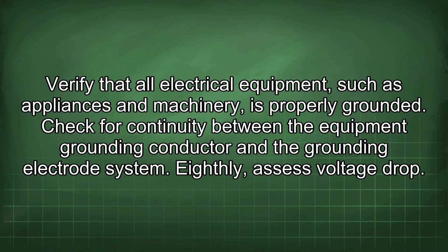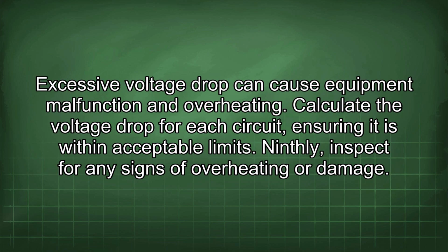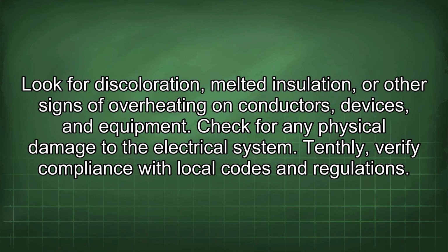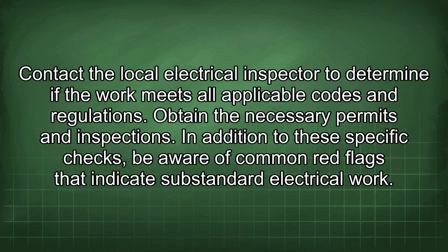Eighthly, assess voltage drop. Excessive voltage drop can cause equipment malfunction and overheating. Calculate the voltage drop for each circuit, ensuring it is within acceptable limits. Ninthly, inspect for any signs of overheating or damage. Look for discoloration, melted insulation, or other signs of overheating on conductors, devices, and equipment. Check for any physical damage to the electrical system. Tenthly, verify compliance with local codes and regulations. Contact the local electrical inspector to determine if the work meets all applicable codes and regulations. Obtain the necessary permits and inspections. In addition to these specific checks, be aware of common red flags that indicate substandard electrical work.